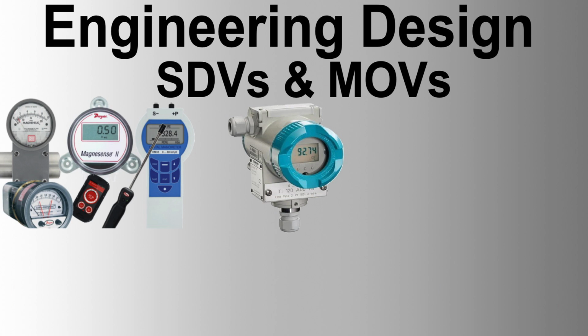Local accumulator volume tank. Where specified in data sheets, the valve shall be supplied with an accumulator size to prevent valve operation in case of utility supply failure. Accumulators shall generally be sized for 3 complete valve operations or 3 hours of duration, whichever is the greater duty. Accumulators shall be carbon steel, complete with nitrogen precharging facility, lockable drain valve, and pressure gauge.